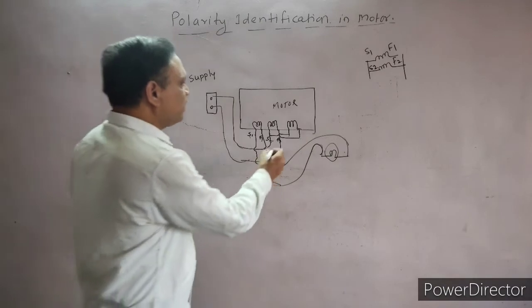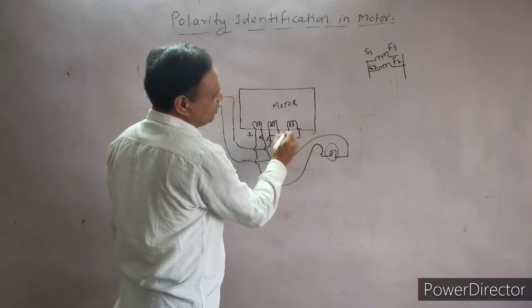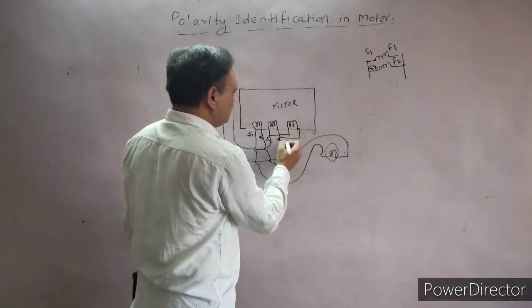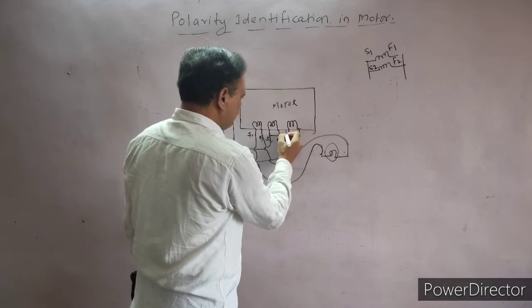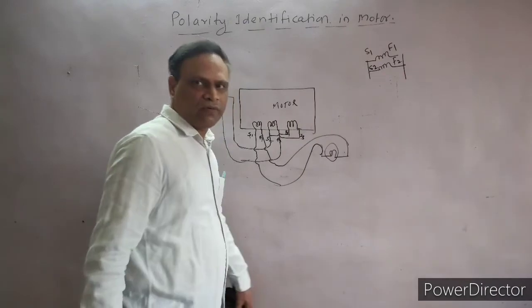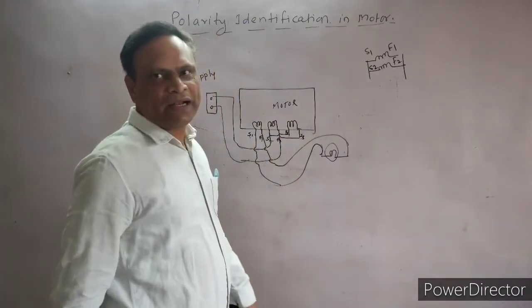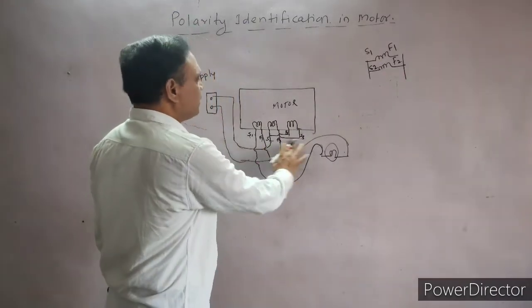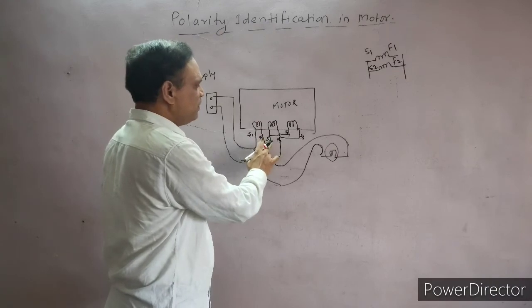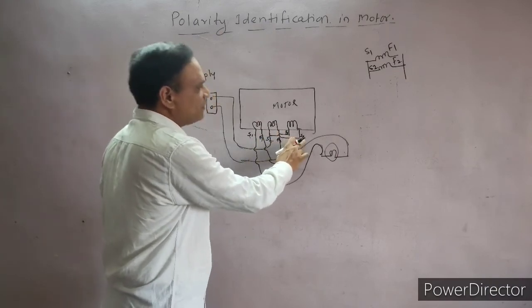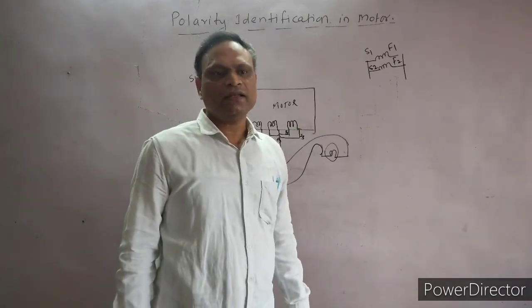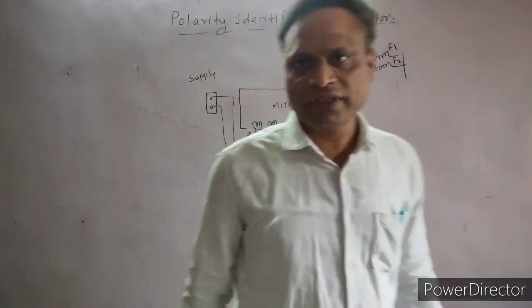Since the lamp didn't glow, the connection is in reverse — series opposition — which means this is the finishing end and this is the starting end of the third coil. In this way we can find out the polarity among all terminals. Once identified, we can mark them: this is A1, this is A2, this is B1, this is B2, this is C1, and this is C2. Accordingly, we can now make star or delta connections. Thank you very much for watching.